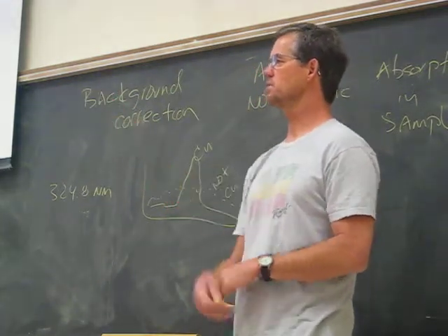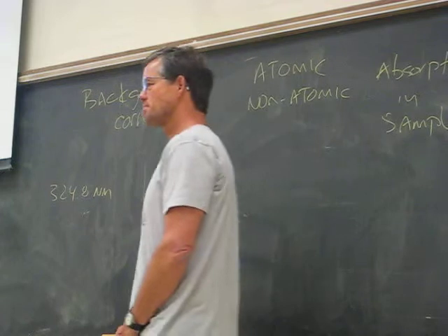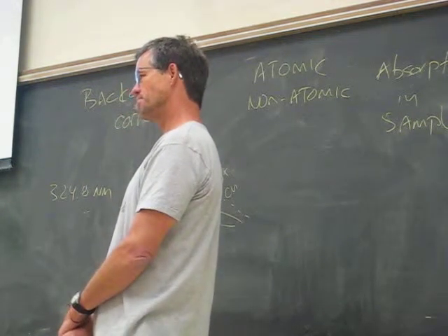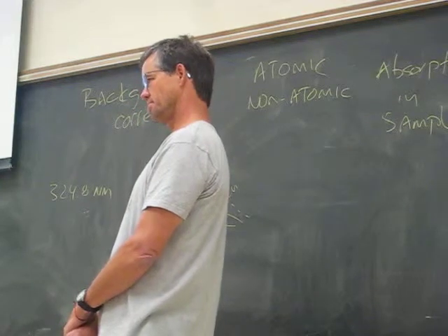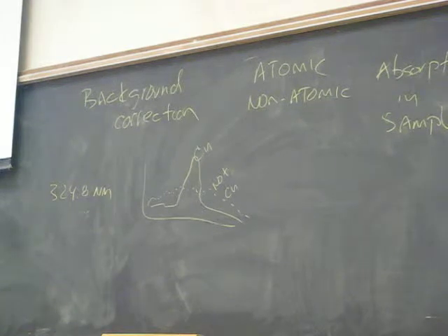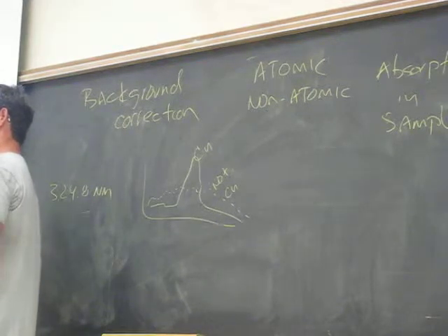You have an alternating signal from the rotor, so that you see the hollow cathode lamp signal, and then you alternate with the D2 lamp. The D2 lamp will excite everything, and the hollow cathode lamp will mainly excite the analyte along with the background. So you take the spectrum from the hollow cathode lamp and you subtract the two, and then select for just the analyte.